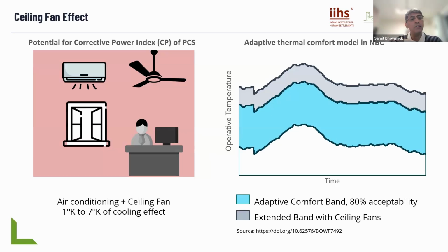What this effectively does is allow us to run our chiller plants at much higher temperatures. So if you were operating a place at, say, 24 degrees, you might now be able to set it at 26 degrees, and with the use of a fan you can still feel comfortable. This has a very high impact on energy consumption. Every degree of increase in set point temperature is about a 3% improvement in efficiency.